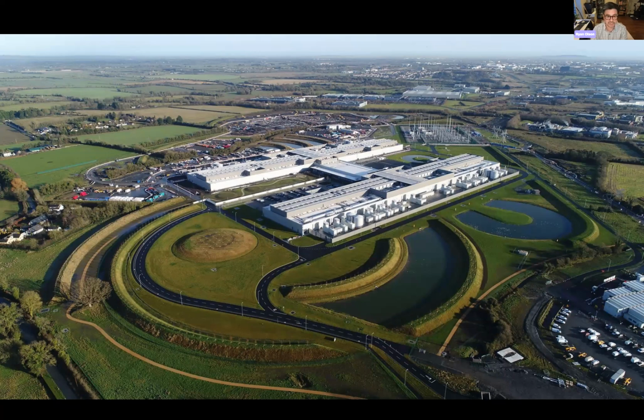So on the screen here is an overhead view of a typical Meta data center building. You're talking about 1 million square feet under the roof of a building. It's a quarter mile long lengthwise. You see it's in an H shape with the data halls on the sides there and an administrative and loading dock area in the middle. And there are multiple data halls along each side. There are 4 on each side, each of which holds thousands of racks and tens or hundreds of thousands of servers. These buildings are measured in megawatts of capacity, with between 10 and 100 megawatts for a site being typical.